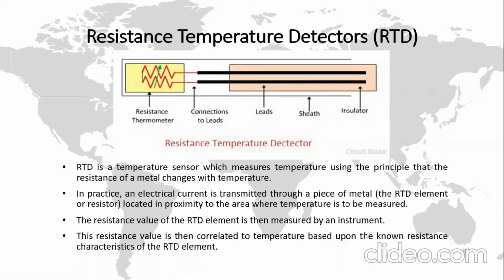Today I would like to explain one type of transducer, which is the resistance temperature detector, RTD transducer. RTD is a temperature sensor which measures temperature using the principle that the resistance of metal changes with temperature. In practice, electrical current is transmitted through a piece of metal, which is the RTD element or resistor, located in proximity to the area where temperature is to be measured. The resistance value of the RTD element is then measured by an instrument. The resistance value is then correlated to temperature based upon the non-linear characteristic of the RTD element.